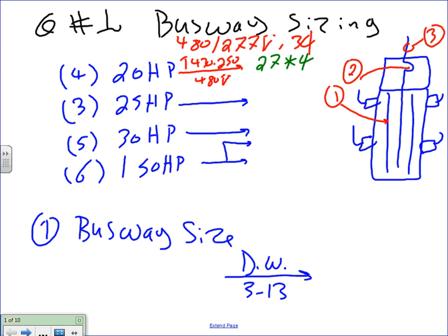If you go to the 25 in the same table, you're going to get 34, and you're going to multiply it by 3. And Chris, we multiply them by 3 because we have 3 of them. If you go to the 30 horsepower, guys, the same table, you're going to get 40, and you're going to multiply it by 5 because we have 5 of them. The 150, I split it into 2. Anybody remember why we split the largest, fattest, fluffiest motor into 2? Because we're going to add 25% on the largest motor, okay? I have 6 of them, though. I want to split it into 2 sections.